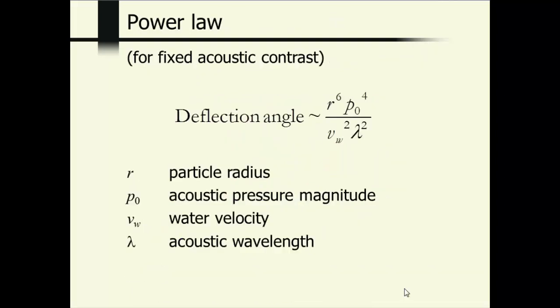And this shows that power law. That power law is for fixed acoustic contrast. And the deflection angle is proportional to the sixth power of the particle radius, the fourth power of the acoustic pressure, inversely proportional to water velocity squared and wavelength squared. And this is exactly the sort of power law which will be very useful in deciding what parameters to use for separation and for how to design a particular device.